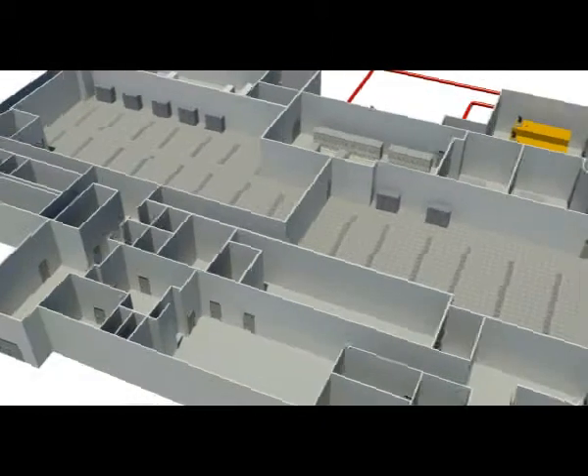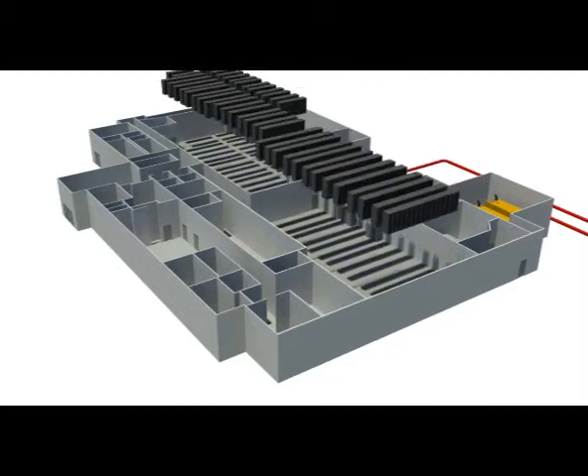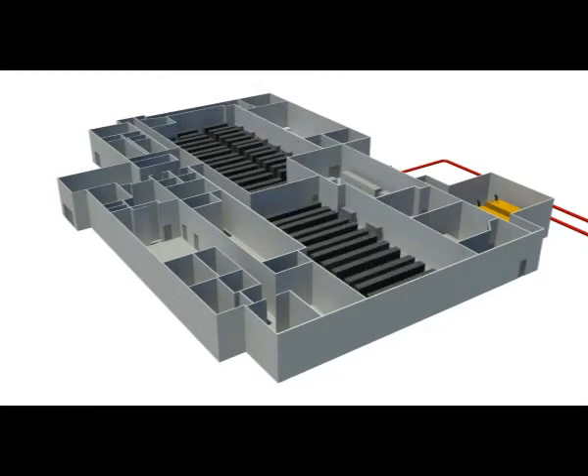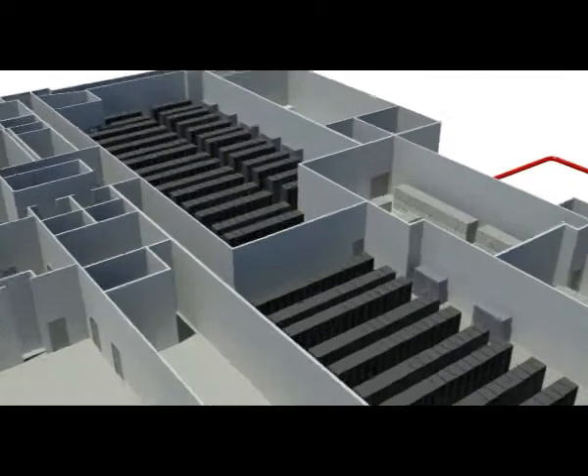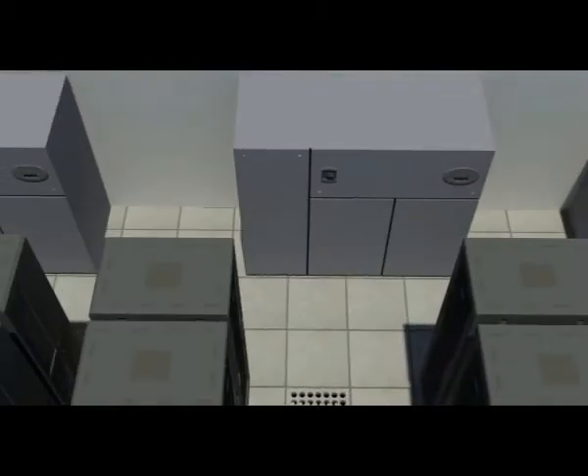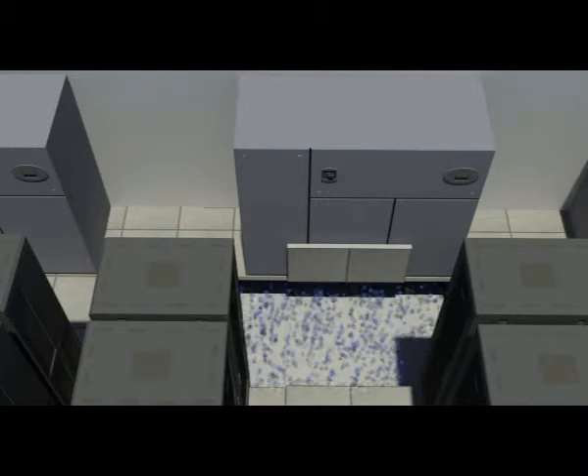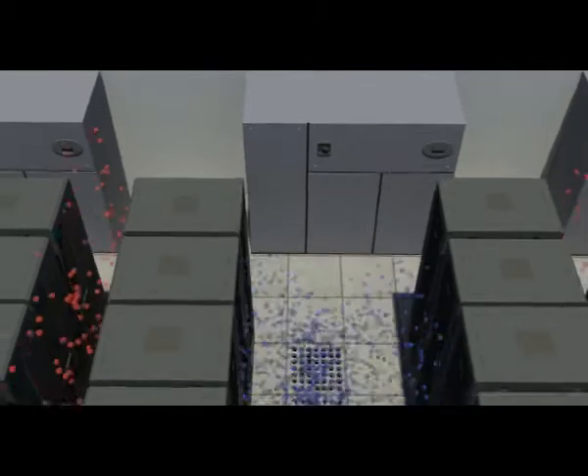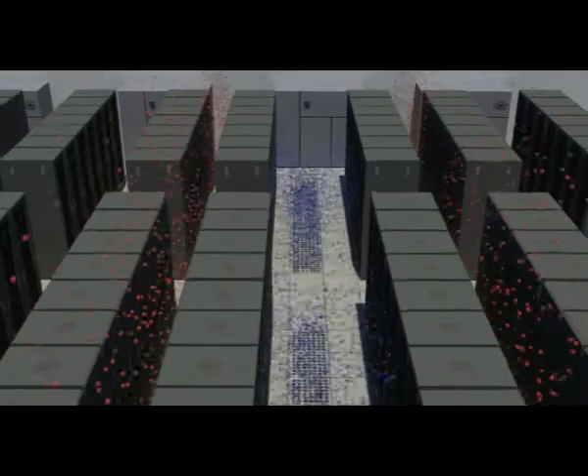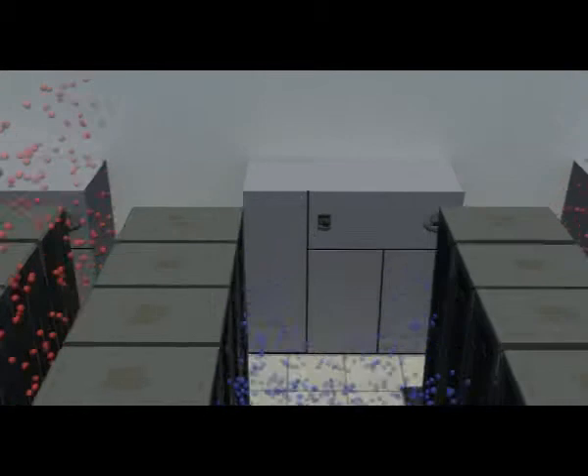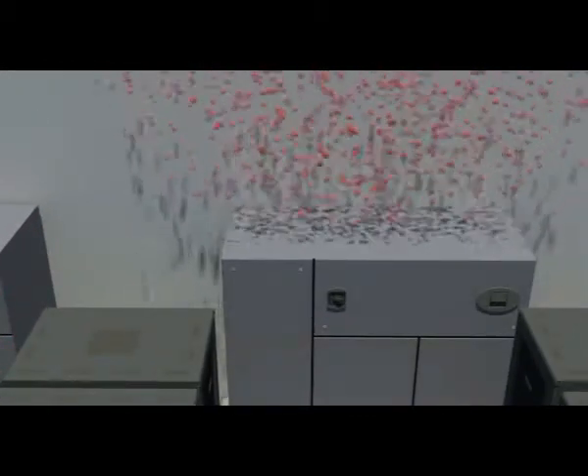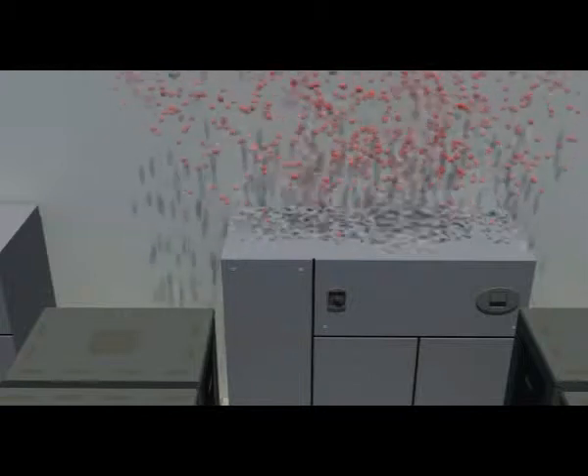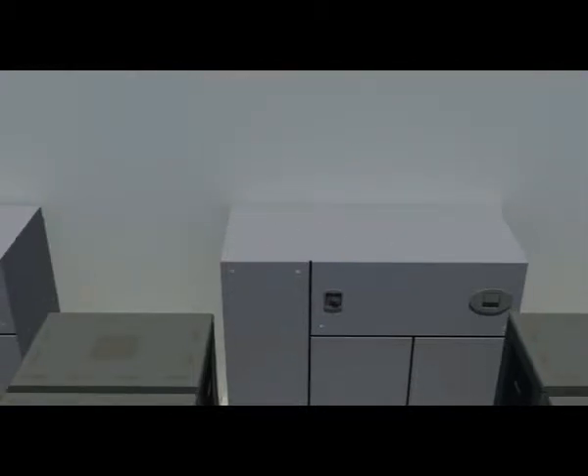Server cabinets are positioned in parallel rows, back to back, creating a hot aisle, cold aisle configuration that efficiently keeps hot air circulating out of the cabinets and cool air circulating in. Cold air is pushed from the computer room air conditioner unit under the floor, creating a high-pressure system that forces the chilled air up through air vents in the cold aisles. That chilled air is pulled in through the front of the server cabinets and then fanned back out as hot air in a hot aisle. The hot air rises to the ceiling and then enters the CRAC units for the cooling process to start again. The result is an environment that is always the perfect temperature to keep customer equipment safe from humidity and overheating.